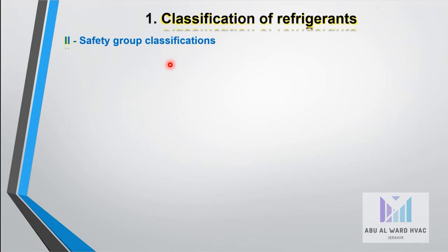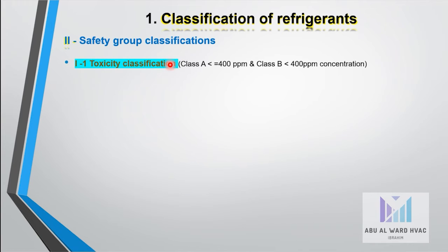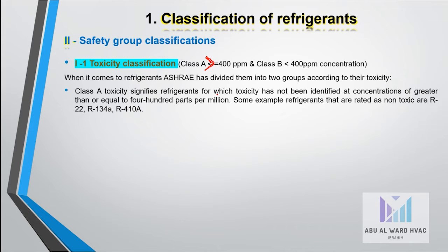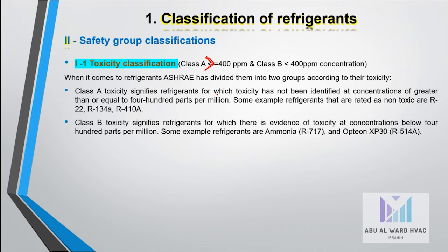Safety group classifications: there are mainly three classifications in this category. The first is toxicity classification. Toxicity class A is when the concentration in the refrigerant is greater than 400 ppm, and class B is less than 400 parts per million. Examples of class A include R22, R134a, and R-410A.